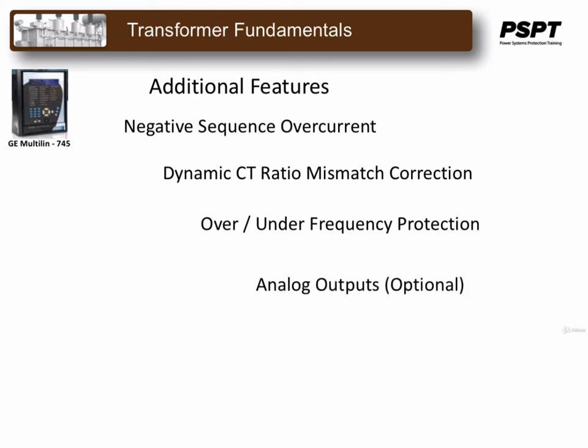Analog outputs, which are optional, include 7 transducer output channels allowing individually programmed outputs for ranges of 0 to 1 milliamp, 0 to 5 milliamps, 1 to 10 milliamps, 0 to 20 milliamps, and 4 to 20 milliamps. Channels are assigned to any measured parameter. All feed-in CTs are connected in a Y configuration for simplicity. Then all phase and magnitude corrections, as well as zero sequence current compensations, are performed automatically based on a choice of over 100 transformer types.